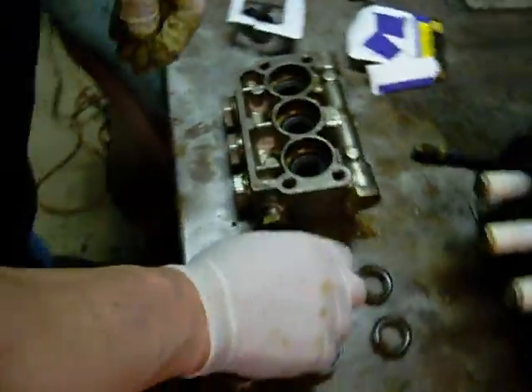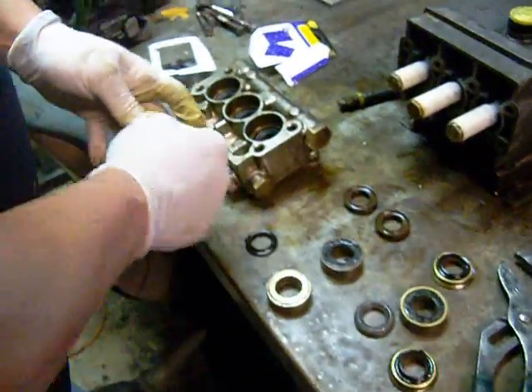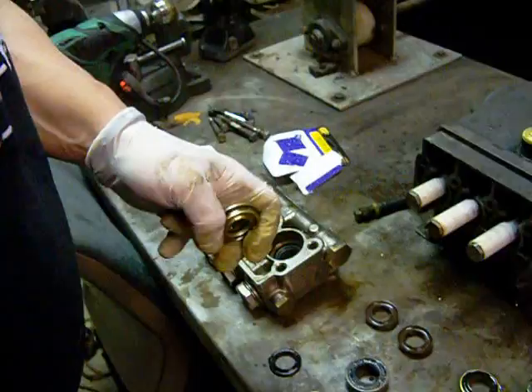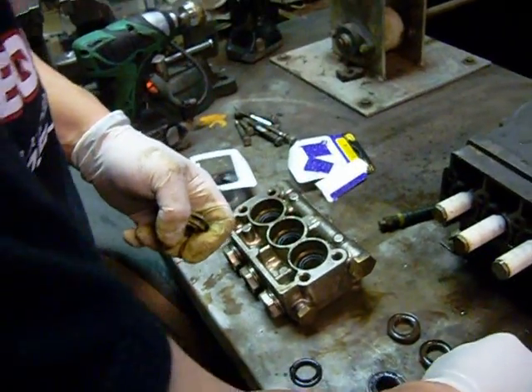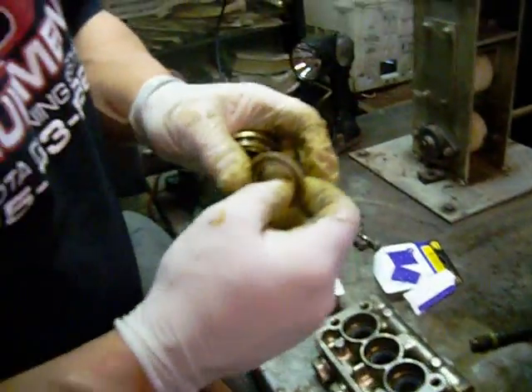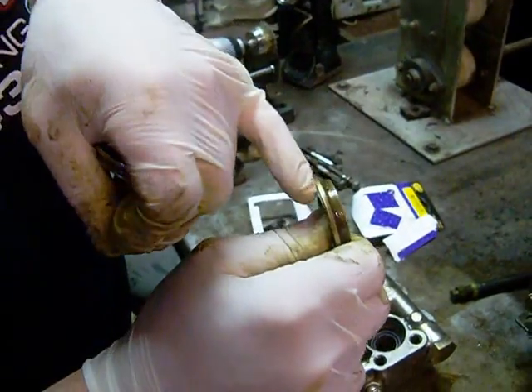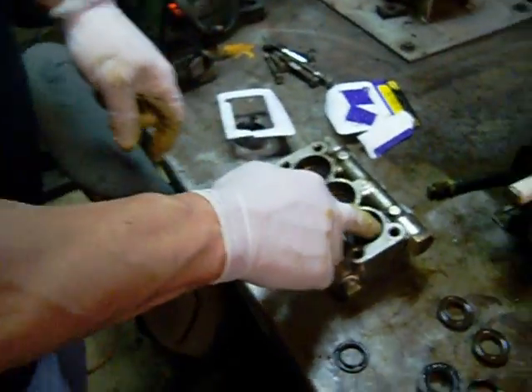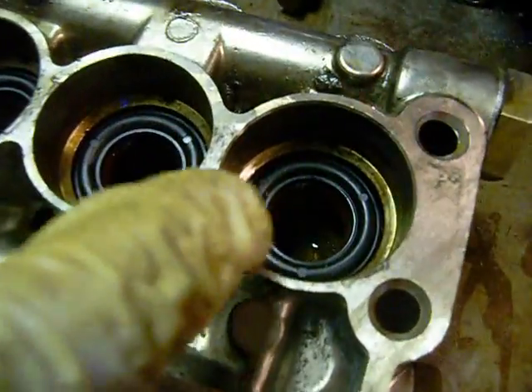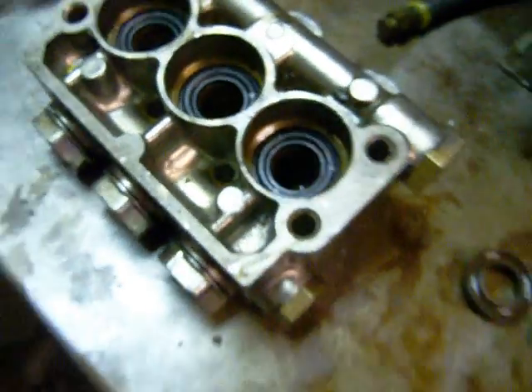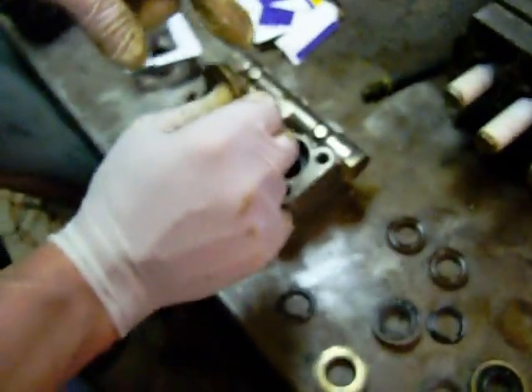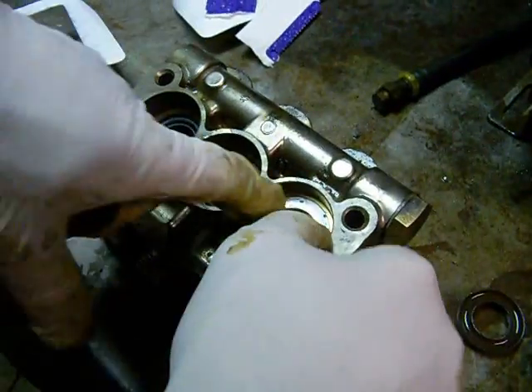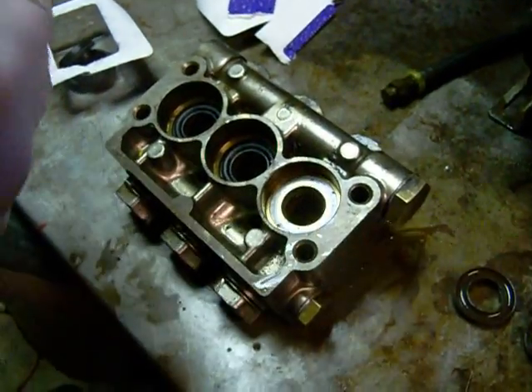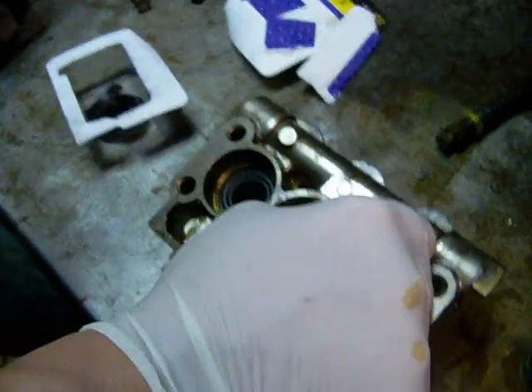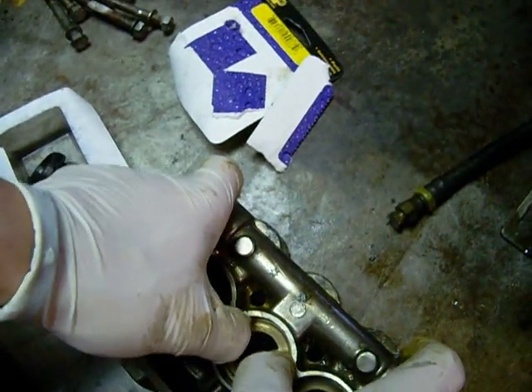Then we're going to take our brass retainers that hold our high pressure seals down. They have little holes top and bottom, and we're just going to line the holes up, or get them as close as possible. That's a weep hole to show you if your seals are starting to go bad, so we want to line them up to get that weep effect when the seals start to go. We'll set them all in and make sure they're down.